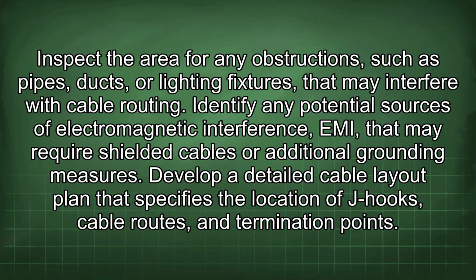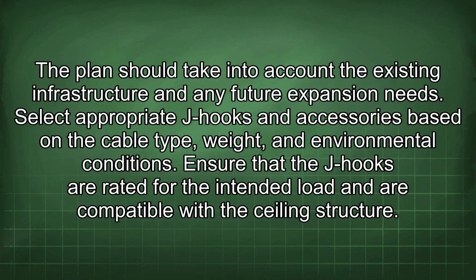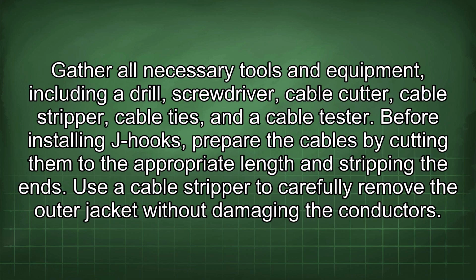Develop a detailed cable layout plan that specifies the location of J-hooks, cable routes, and termination points. The plan should take into account the existing infrastructure and any future expansion needs. Select appropriate J-hooks and accessories based on the cable type, weight, and environmental conditions. Ensure that the J-hooks are rated for the intended load and are compatible with the ceiling structure. Gather all necessary tools and equipment, including a drill, screwdriver, cable cutter, cable stripper, cable ties, and a cable tester.